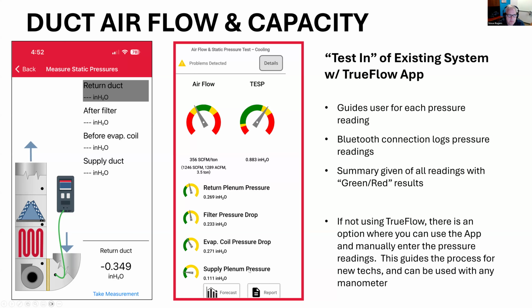That's great. 0.11. I wish every system had that low of a static pressure in the supply plenum. Evaporator coil is a little higher, but that's the existing one that we're probably going to replace. And the filter is also a little high, but usually a new system is going to get a new size filter when it gets replaced. The return plenum pressure, that's in the yellow, and that's really the highest one of the four. So if I wanted to renovate this system, that's where I would focus my efforts.